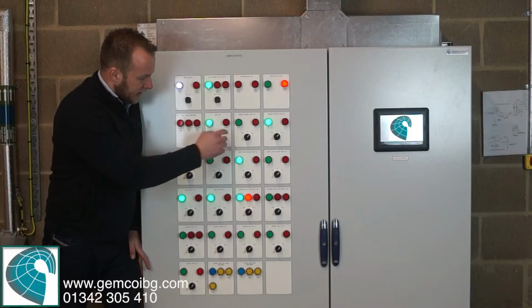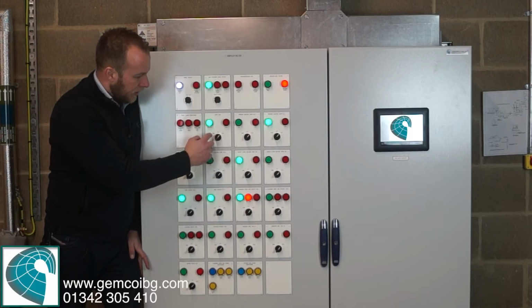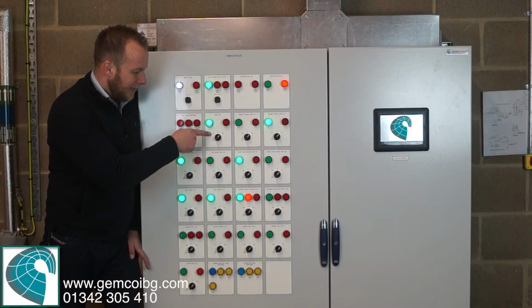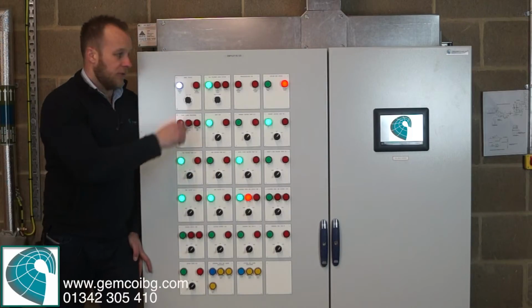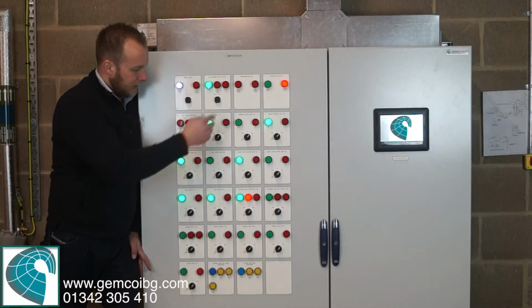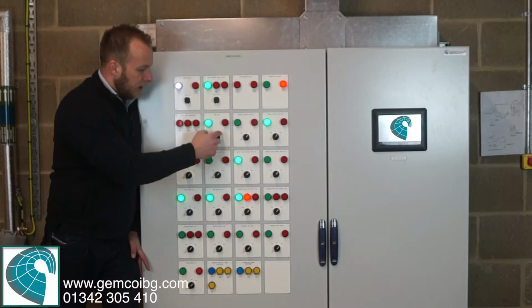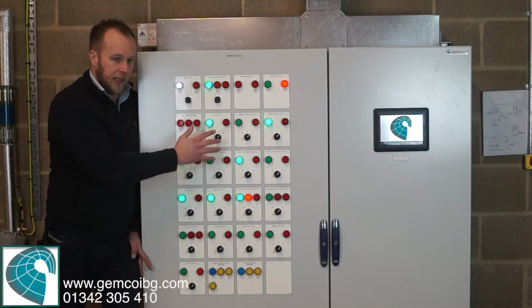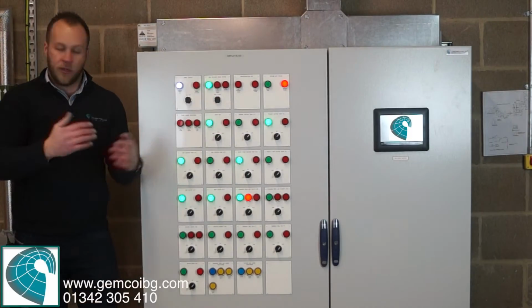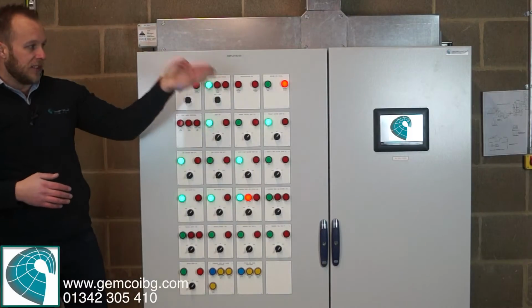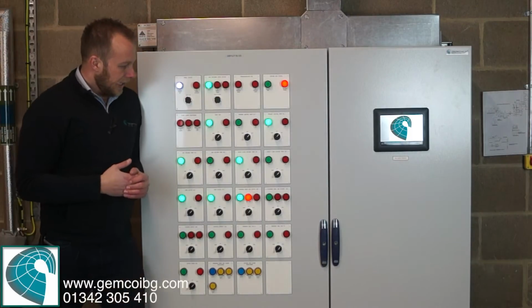And all of these switches, as I go on, all of these switches have got three positions. Hand means manual, but respecting these safety circuits. Off is off, obviously, and auto is respecting the safety circuits, but under time switch control. So it'll go on and off on the occupancy times, which I'll show you how to use in a bit.